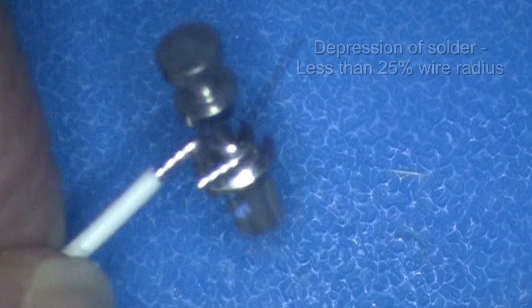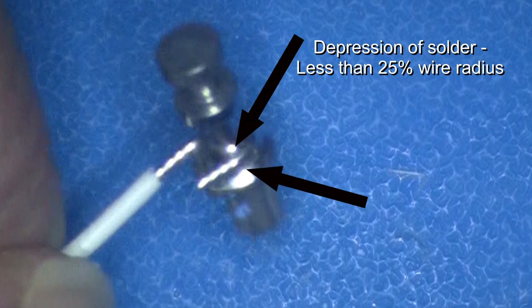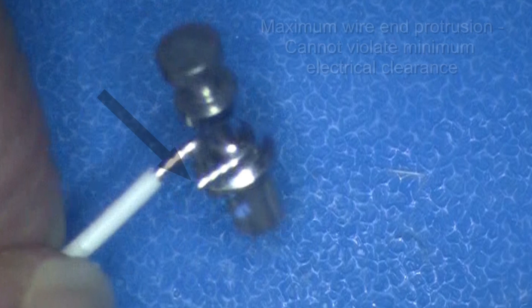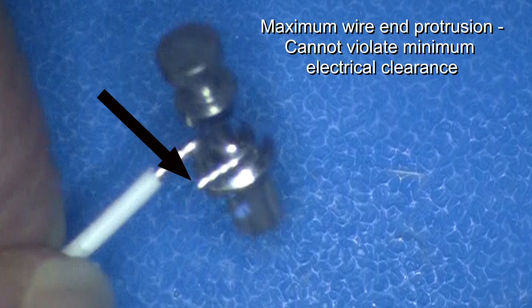Solder should rise between the wire and the terminal and along the terminal base so that any depression between the surfaces is not more than 25% of the radius of the wire. The end of the wire cannot extend beyond the terminal base far enough to cause a potential short to other parts of the assembly.